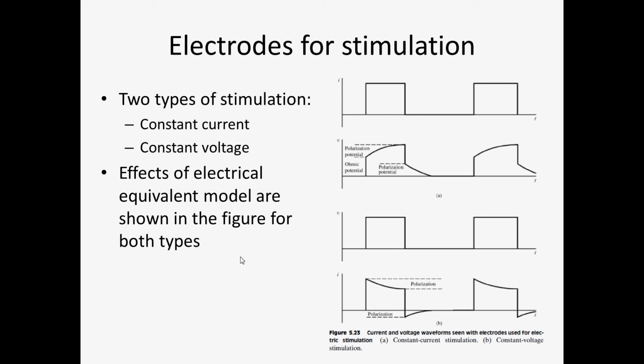Because if there is a large contact impedance, there is a large resistor, and if you make a large current circulate into a large resistor, you're going to create a little stove under the electrodes, which could cause burns, blisters, up to second or third-degree burns. I'm not joking.